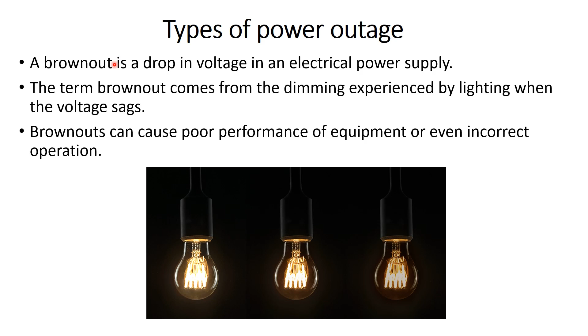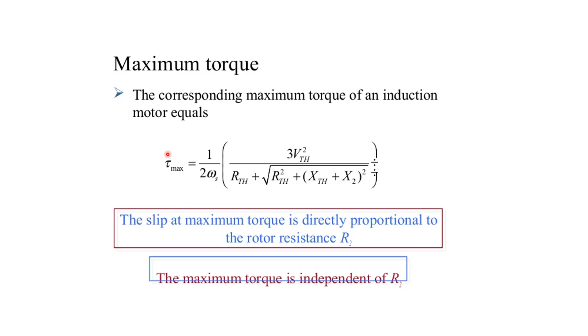So here is another example, which is the torque inside a motor. The maximum torque inside an induction motor, you will see that it is dependent on the voltage squared. So when the voltage decreases, the maximum torque will start to decrease, which means our induction motor will produce lower torque. This happens in the brownout phenomenon, and of course, if the voltage decreases below a certain limit, it can cause undervoltage, which will lead to shutdown of electrical machines.